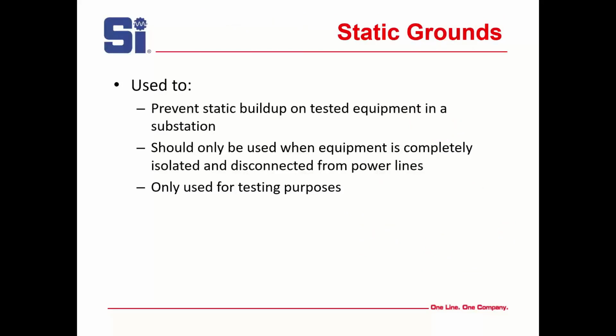Static grounds, though, are a little different. They're typically lighter. They're not used as a personal protective ground. They prevent static buildup on tested equipment in the substation. And that static buildup could be from a nearby line, or it could be from a DC test that you did. So static grounds discharge all that. It should only be used when equipment is completely isolated and disconnected from power lines because they're not intended to carry fault current, and used only for testing purposes, of course.